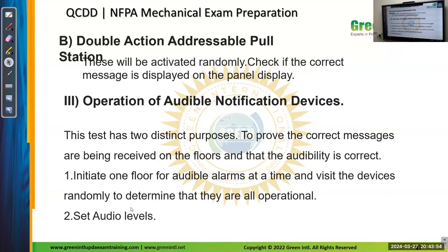So, double action addressable pull station. This will be activated randomly. Check if the correct message is displayed on the panel or not. Double action addressable pull station needs 2 signals to get it activated.